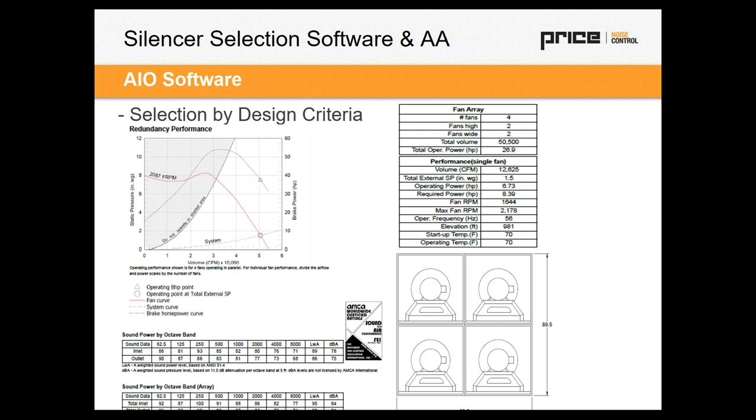And in this case, it might be at the design stage, such as this example. You might have a Greenheck fan. In this case, it's an array of fans, quantity of two, a 2x2 array. The overall dimensions are 89.5 inch by 89.5 inch width by height. And the engineer came to me and said, hey, Mauricio, I am bringing air into a power plant with 9 gensets. I'm going to use these fans to bring air in from each side of the building for each generator.